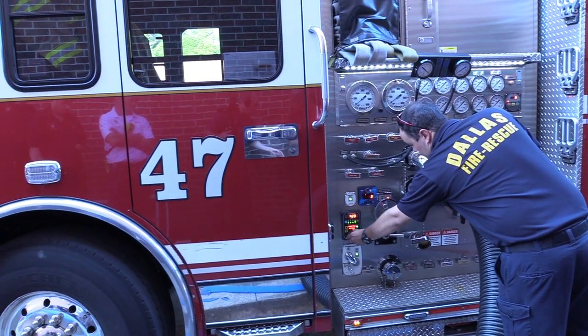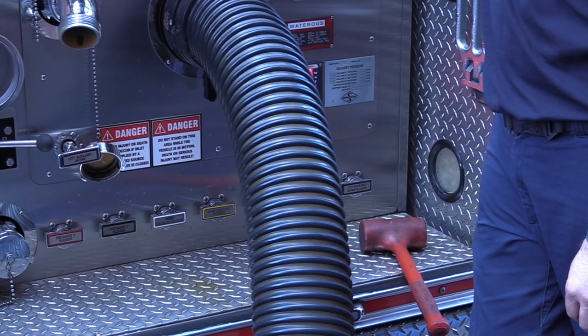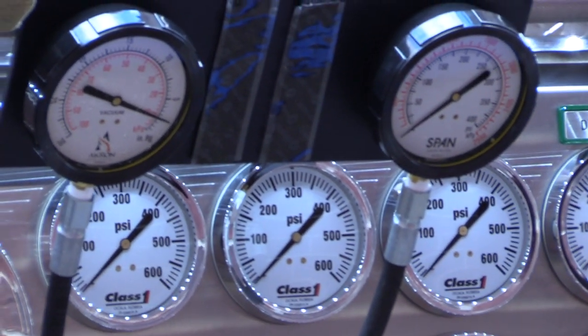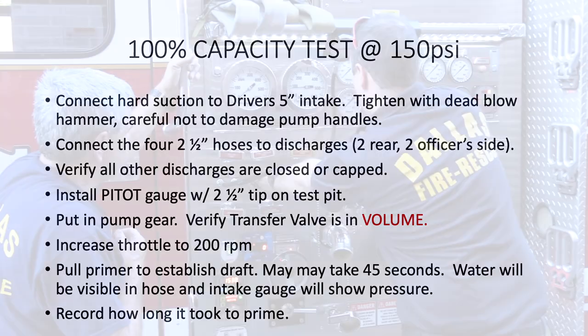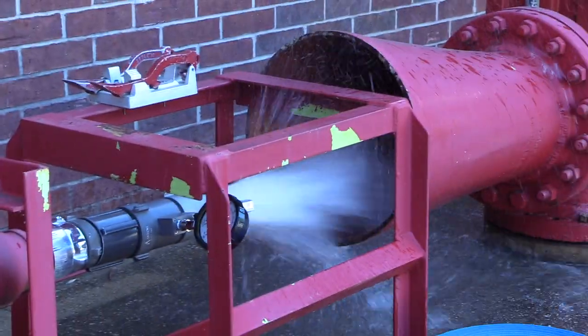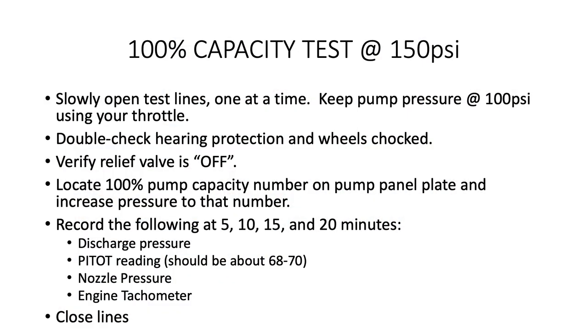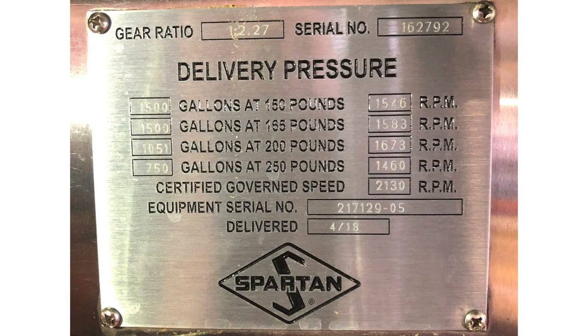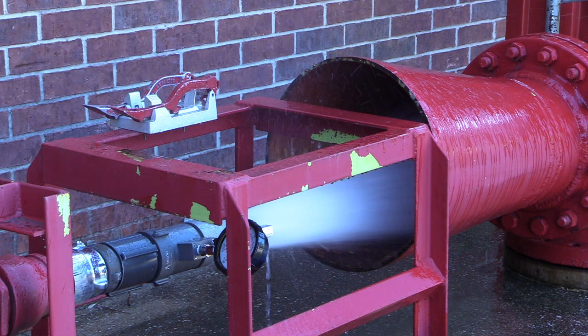Increase the throttle to 200 RPMs. Pull the primer handle and hold until you have established a draft. Water will be visible moving through the hard suction hose and the intake gauge will show pressure once a draft is established. Record how long it took to prime — ideally it will take about 45 seconds. Slowly open each test line one at a time, keeping your pump at 150 PSI by adjusting your throttle. Do one last safety check for hearing and eye protection as well as chalked wheels. Verify your relief valve is in the off position. Locate the pump panel plate — this has all the information you need for the testing of your specific pump.